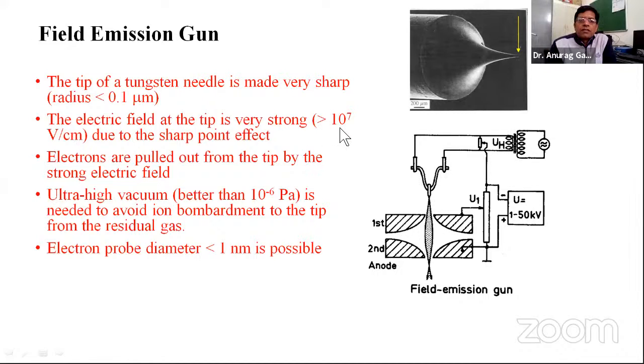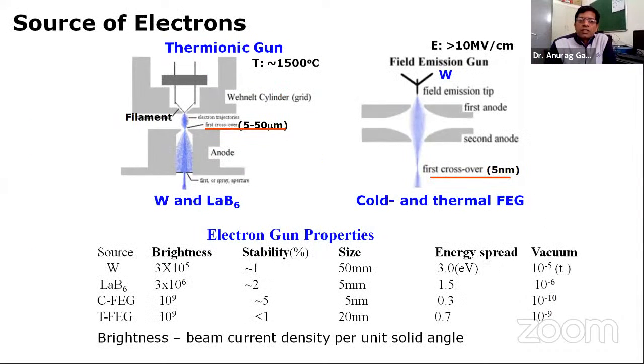So this high electric field we apply, and these electrons are pulled out from the tip under the influence of this high electric field. So this is the field emission gun, and the probe diameter is less than 1 nanometer. That is very important: the diameter of your probe, or the spot size of your beam, will also affect the resolution. So this is the field emission gun.